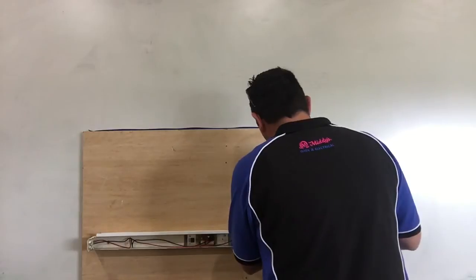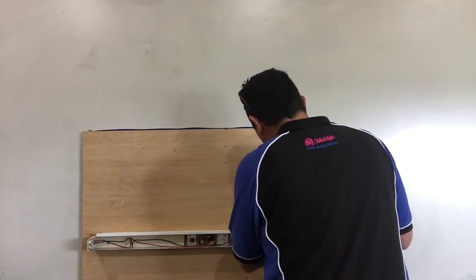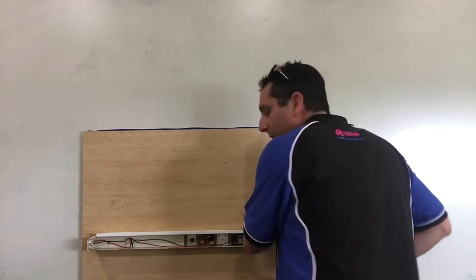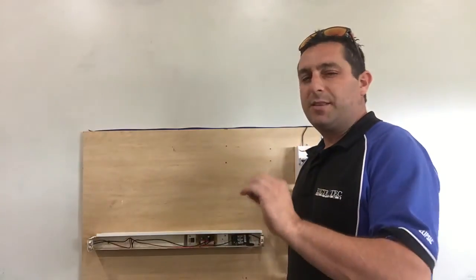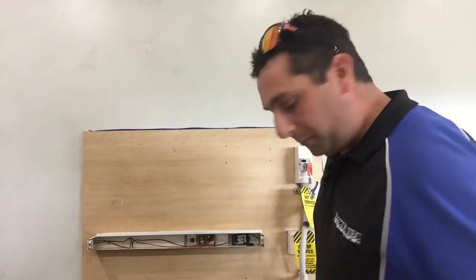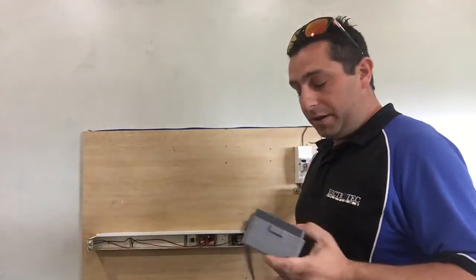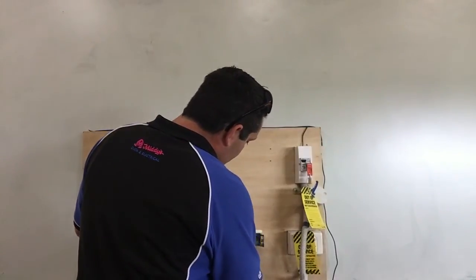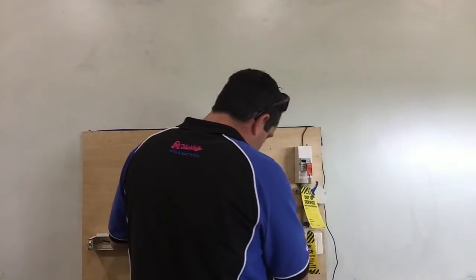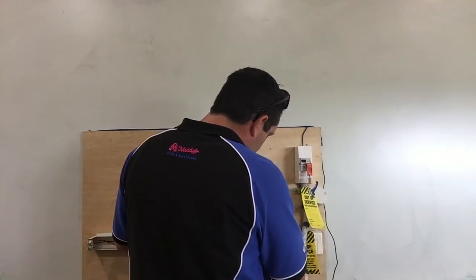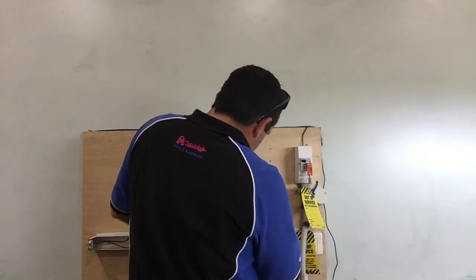Yeah, this is an important thing to remember because those type of appliances with a sheathed heating element can store a bit of moisture in them. Hence why there's a little bit of variance there to be able to have that little bit of insulation resistance being slightly lower. The other thing we need to check is the earthing system of our appliance. So from the earthing terminal to the stud, on the 3 ohm scale, we want this to be down to 0.